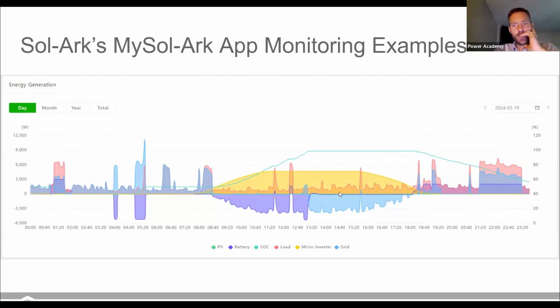And then this customer has a time of use enabled, so it's not using those batteries at all from about 1 o'clock until 6 p.m. And then those batteries are kicking in to cover the loads later in the day, and you see the battery percentage drop off.